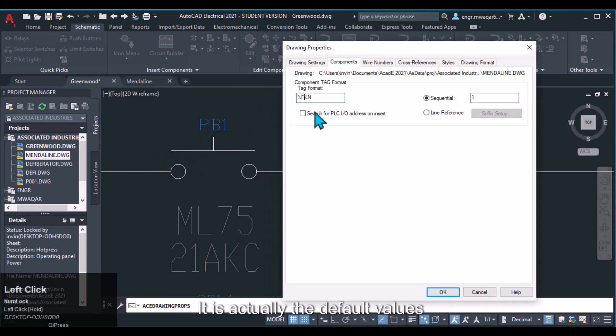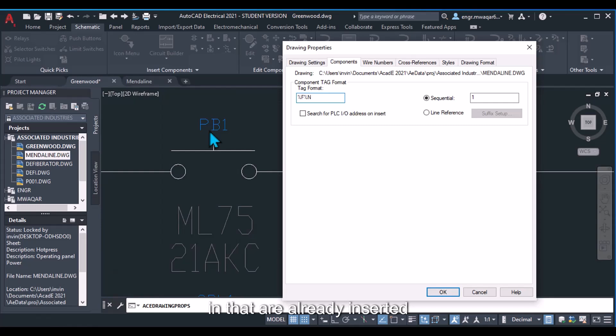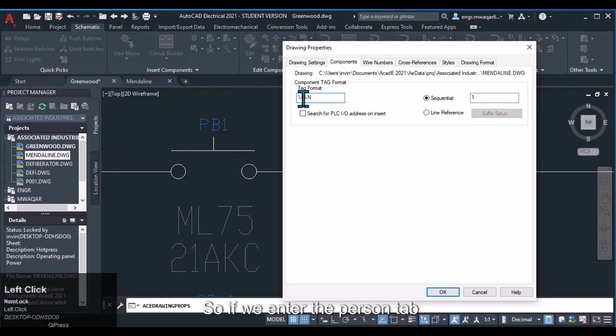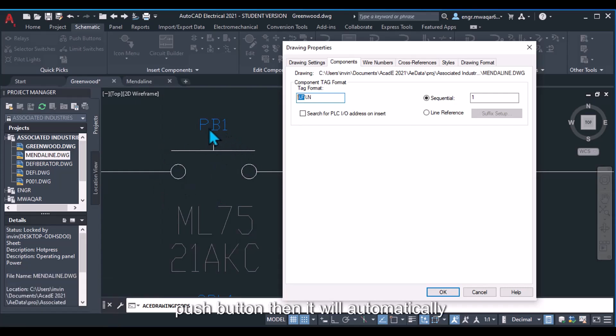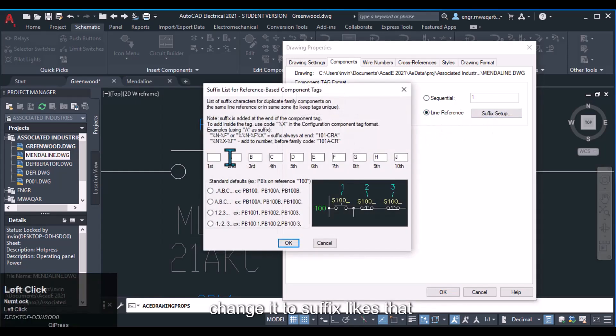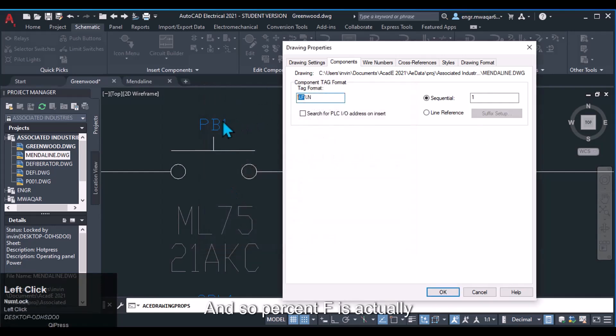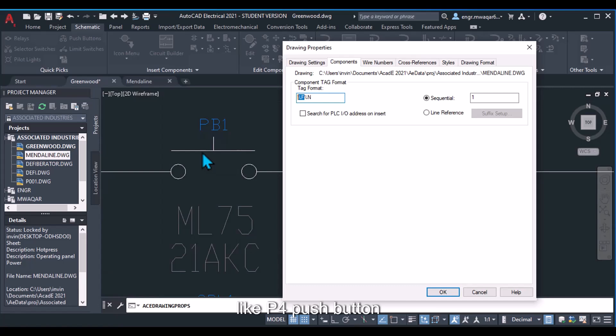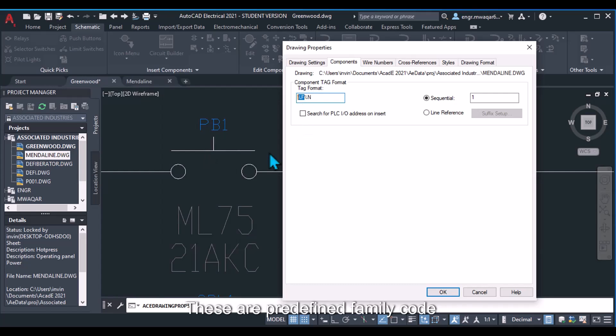The %f represents the component family or code string. These are default values already inserted in the symbol library. So if we use %f when inserting a push button symbol, it will automatically enter a value like PB, and %n shows the sequential number — for example, PB1. We can also change it to a suffix format. %f is predefined: PB for push buttons, CR for control relays, and MT or MTR for motors.